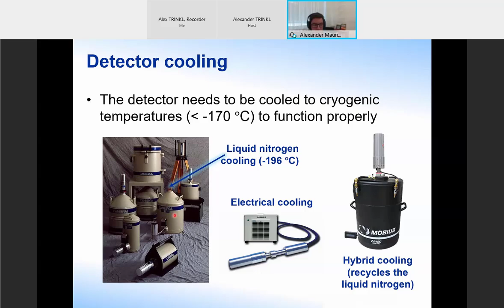to make it less and less work intensive to keep them. What's also come in the last, let's say, 5 to 10 years is hybrid cooling, where you have nitrogen in a tank, and the top part is a system to regenerate that nitrogen using a cooling technology. So you recycle the liquid nitrogen, and in the end you fill it once, and then maybe a year or two later you need to fill it again, compared to filling every week or so with typical nitrogen dewars.